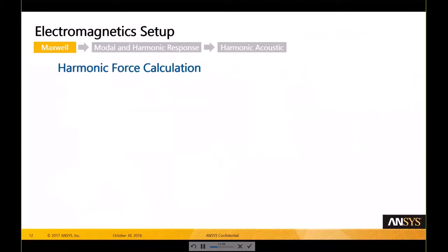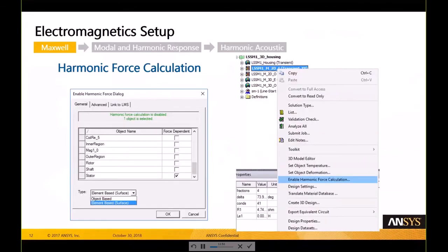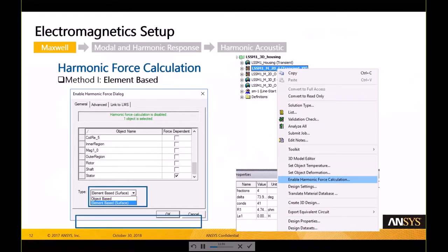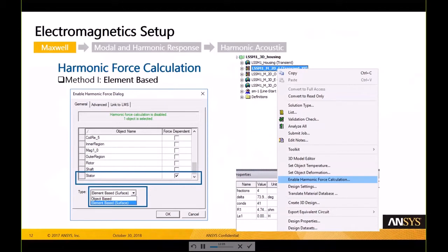In terms of harmonic force calculation, the force calculations happen within our finite element electromagnetic footprint. We have employed two different methods to generate fast harmonic force calculation and also to generate more reliable and accurate force calculation. The first method relates to element-based solution, and based on graphical user interface selection, the user can select the objects within the 2D or 3D domain space which are included into the final force calculation for noise vibration prediction.